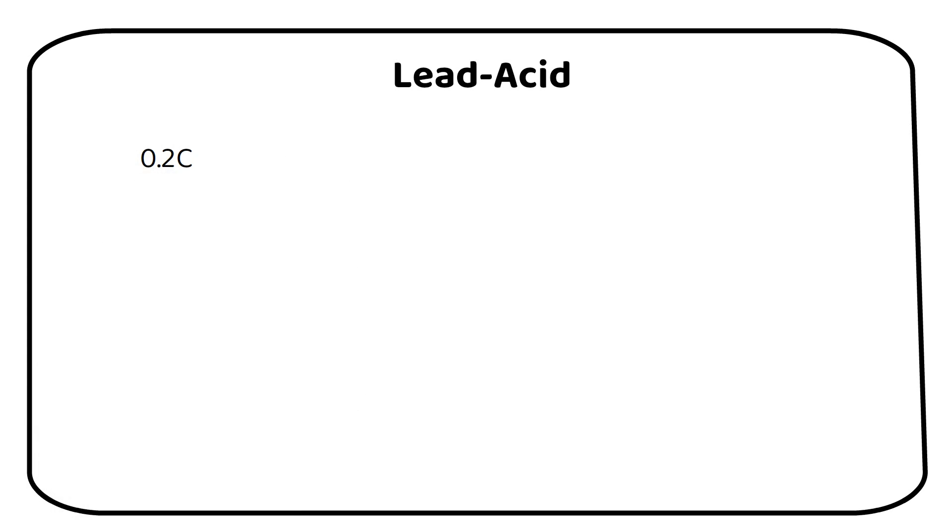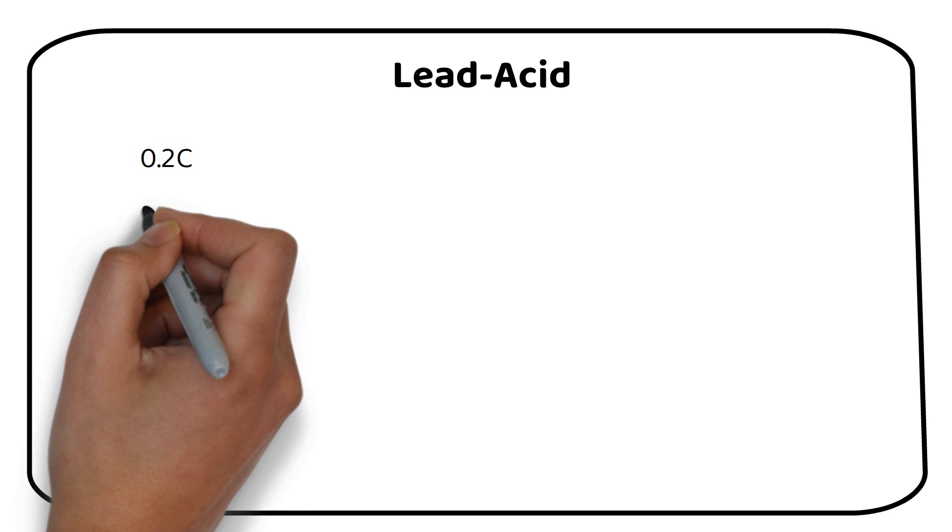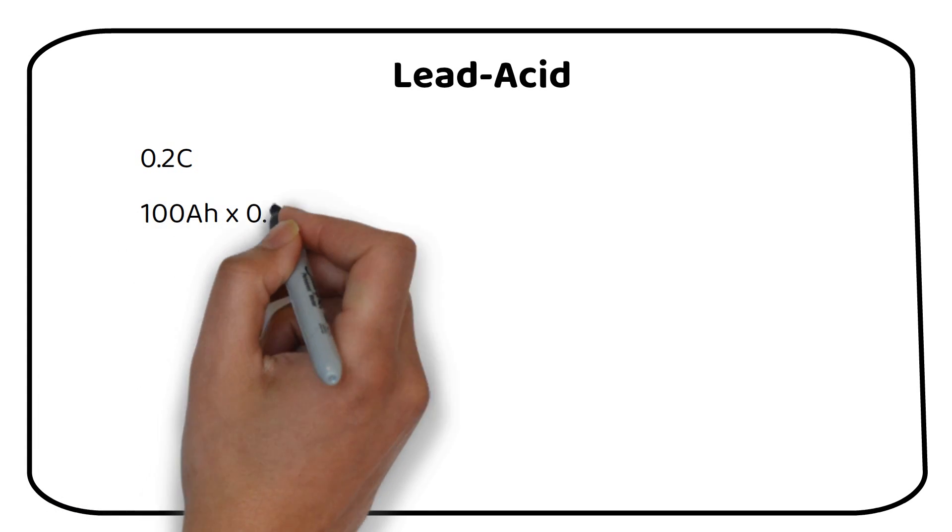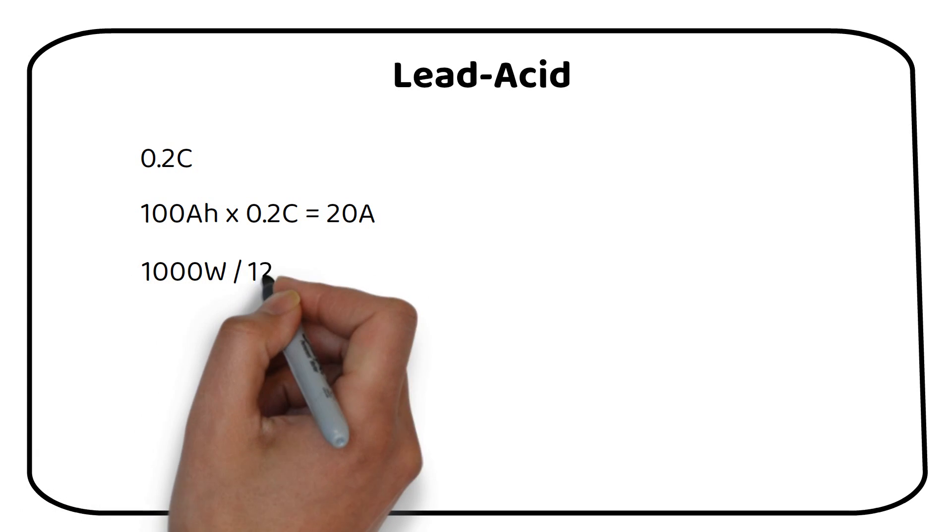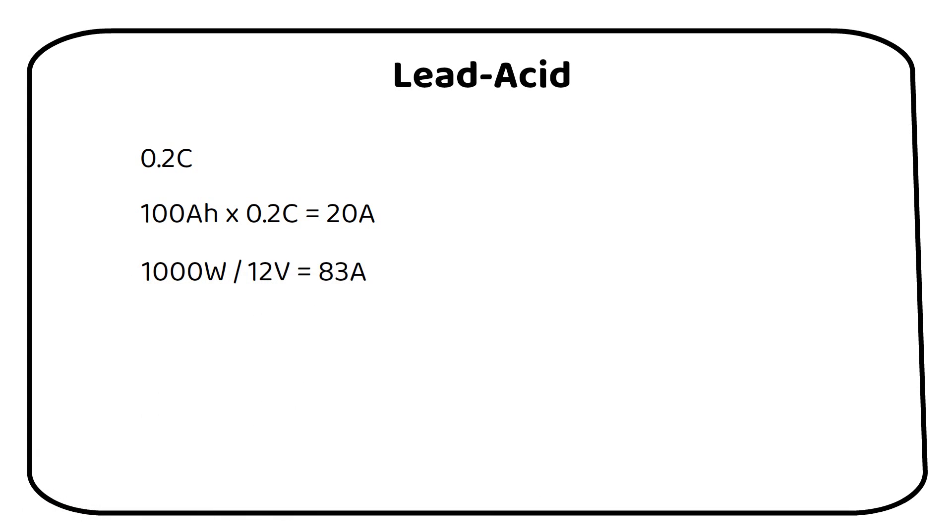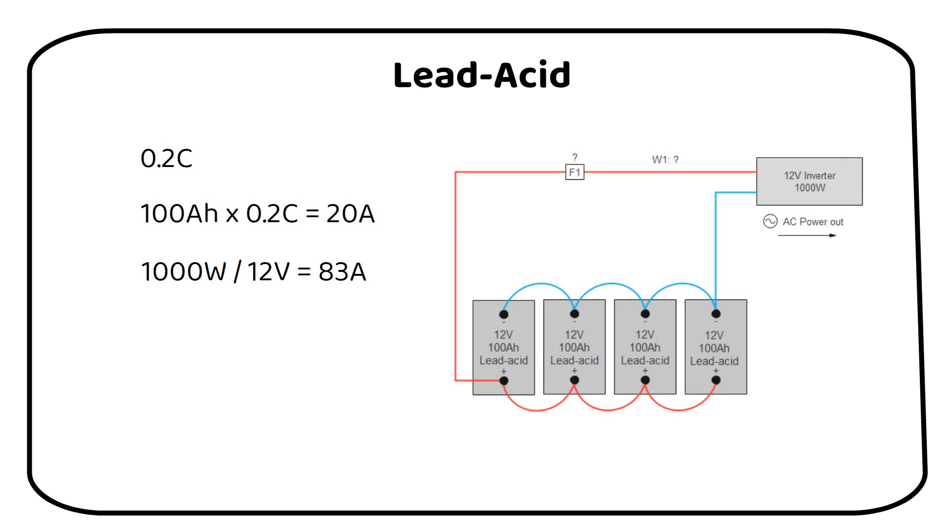The C rate of lead acid battery is 0.2C. This means that the 12 volt 100 amp hour lead acid battery is best to be discharged with a maximum of 20 amps. From our previous calculation we saw that the inverter can draw a maximum of 83 amps. We need 4 batteries in parallel if we want to respect the C rate of the battery.